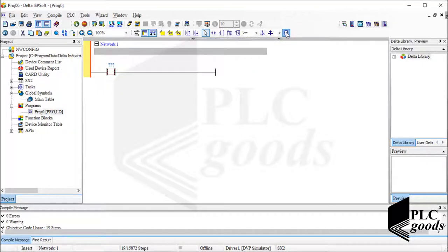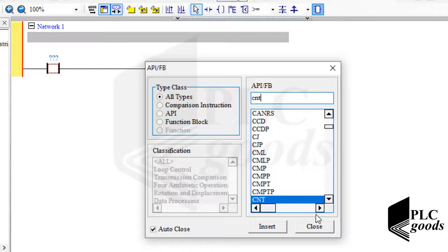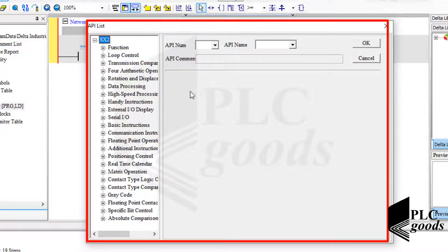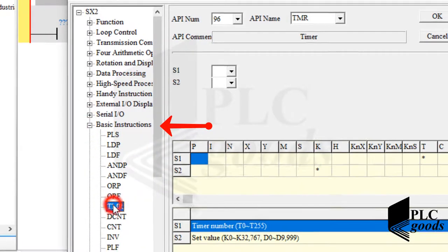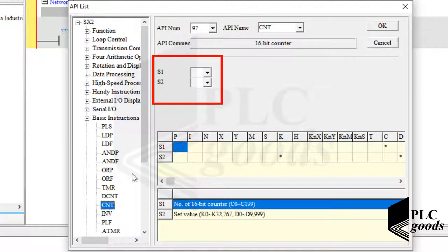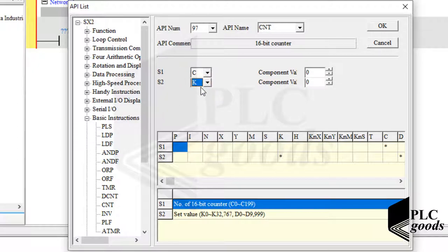I can click on the icon and find the counter instruction in the window — its name is CNT. Another way is to double-click on the program and find the counter instruction in the categories window. The counter and timer instructions are both inside the basic instructions category. The counter instruction has two inputs, S1 and S2, like the timer. I'll select the first counter C0, then determine a number — the first choice enters a number directly, the second choice D refers to a memory location on the PLC. I'll select the first option and enter the number 5.